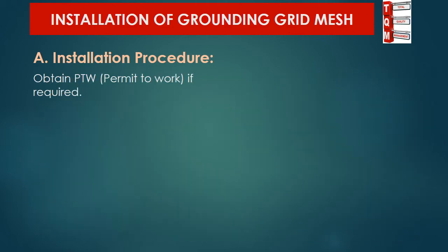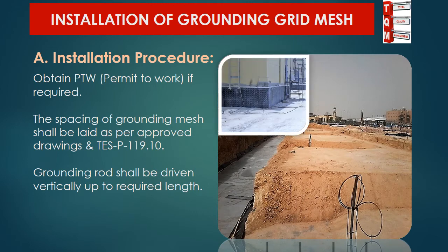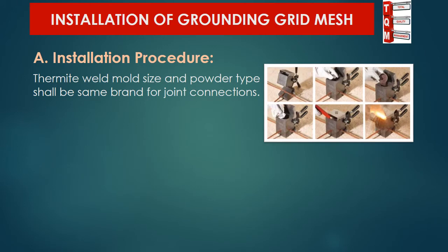If required, obtain a permit to work from the competent authority before starting the grounding mesh activity. The spacing of the grounding mesh varies from 3 meters to 15 meters as per soil conditions, but shall be laid as per approved drawings. The grounding rod shall be driven vertically up to the required length and height. Take care when performing joint welding that the thermite weld mold size and powder type shall be the same brand for joint connections.